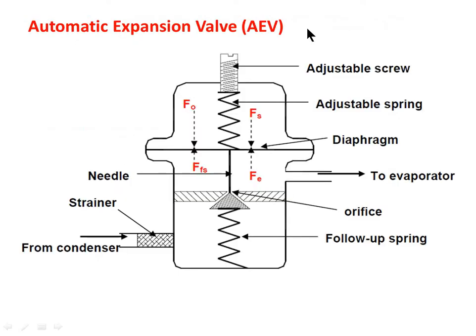Next are automatic expansion valves (AEV). The operation of the valve is automatic once the tension of the spring is adjusted. The components include an adjustable spring, adjustable screw, diaphragm, needle, strainer, orifice, follow-up spring, line from condenser, and line to the evaporator. Once the spring tension is set for the desired evaporator pressure, the valve will automatically regulate the flow of liquid refrigerant into the evaporator, maintaining the desired evaporator pressure irrespective of evaporator loading.